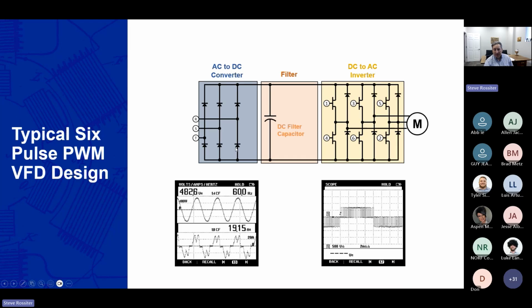Well, the way this works is you've got, in this case, a 3-phase waveform here. When your first wave is increasing in voltage, where it goes through the diode and it overcomes the level of bus voltage, then it commutates on, and that capacitor now swallows that current. That is what I kind of refer to as the gulping effect, which causes this voltage sine wave, which is very clean and pure, to have a current sine wave, which is not sinusoidal and is gulping like you see in this bottom slide. And so that's really the impetus of some of the challenges associated with VFDs on the line side of the VFD: you're charging capacitors that are being discharged by the inverter section, and as fast as they're being discharged, that diode front end is recharging them in that gulping fashion.